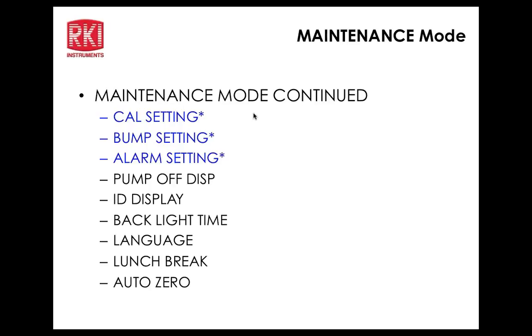Question, Bruce. With that suppression there, in leak check, does that mean it hides that 0 to 1,000? No, there's no 0 suppression when you're in the leak check mode. Can we do that? I don't think there's a setting for that, actually. No, when it's in the leak check mode, it assumes you want the most sensitive test capability, so it doesn't have any 0 suppression.